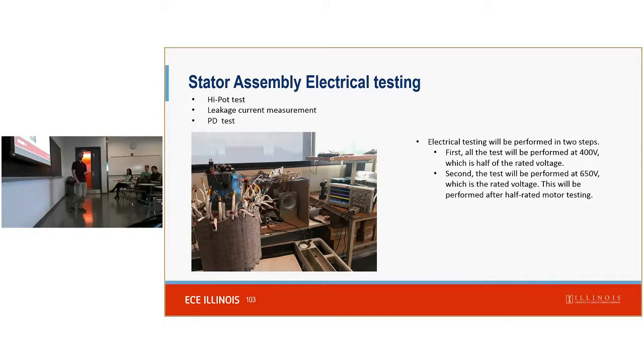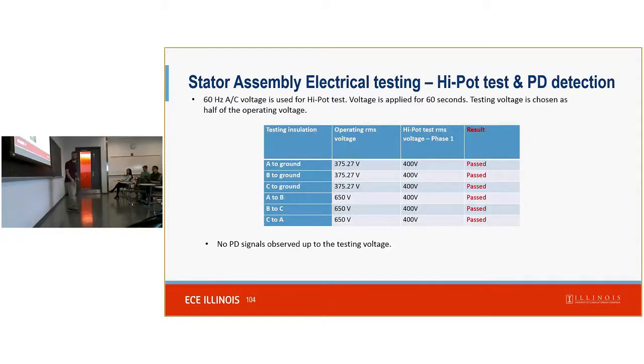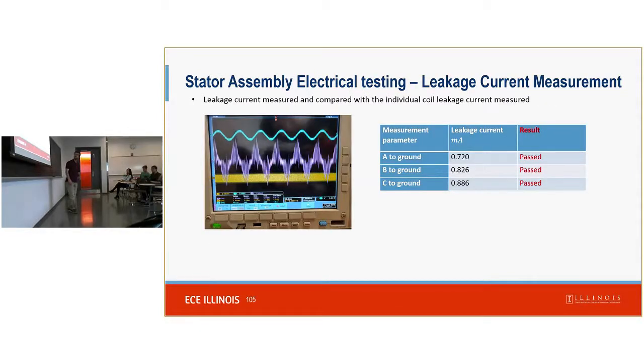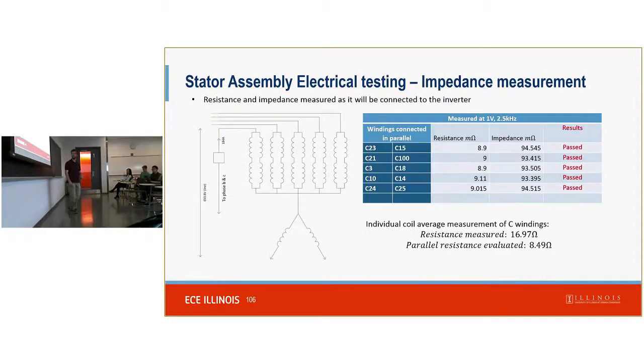However, there's another set of electrical testing. We haven't done full testing up to the full voltage because there's concern that once you pass the breakdown voltage, the coil will be permanently destroyed. And so we tested it to partial voltage and it worked fine at that level. Our plan is to do some initial tests, and then after the initial tests, electrically test it up to full voltage and do more complete tests, to avoid the risk of destroying the machine before we have time to test it. And leakage current was also very low, and impedance measurements as well were within the ranges that we had set.